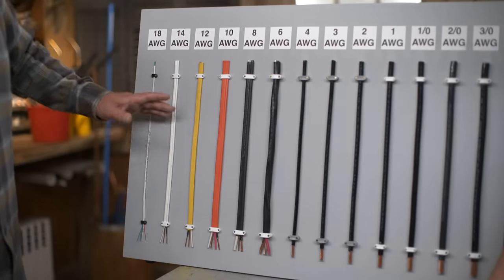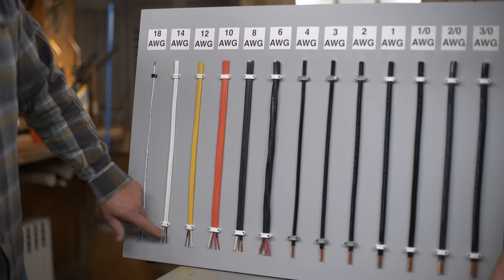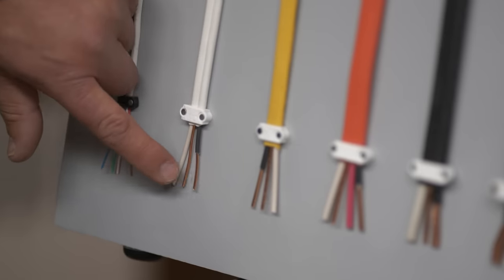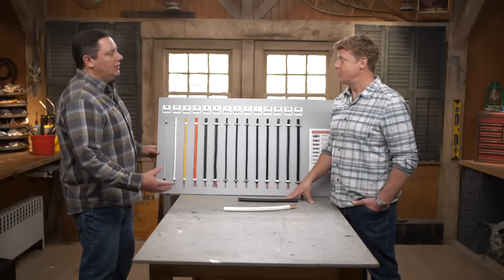So that refers to the number of conductors. The first number is the gauge size — that 14 — but then the two means we have two conductors and a ground. So one, two, and our ground — that's our 14-2. And there might be a third conductor if you have a three-way switch or something like that. Exactly, but it's still the same size — just more conductors in the jacket.